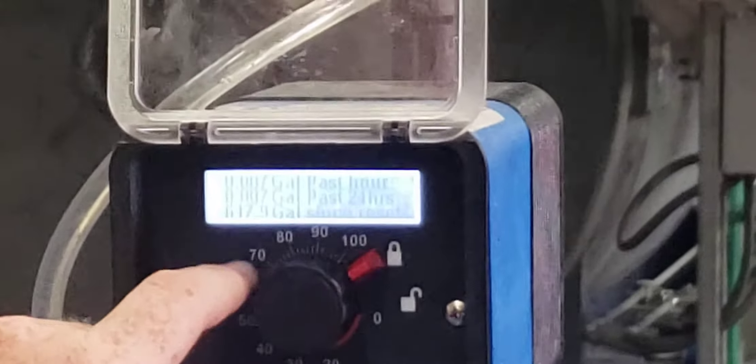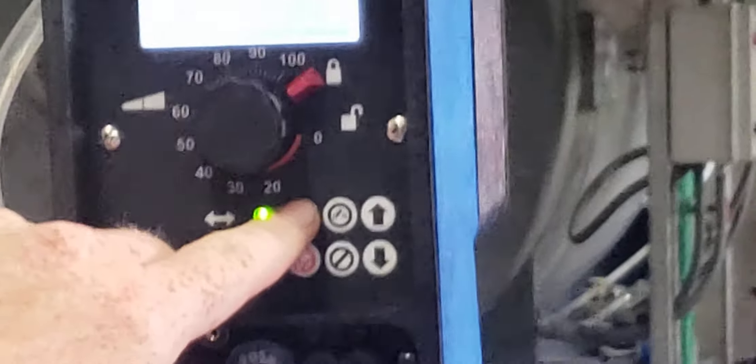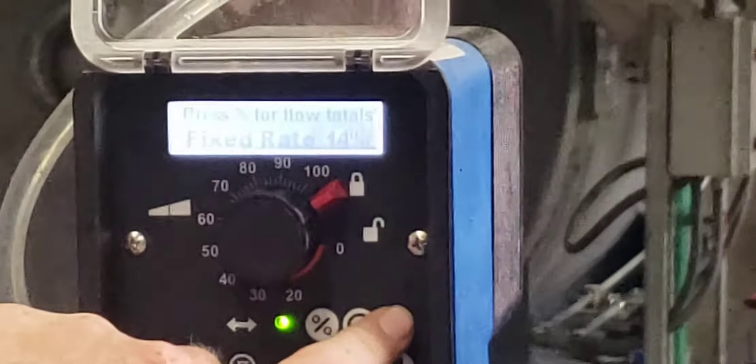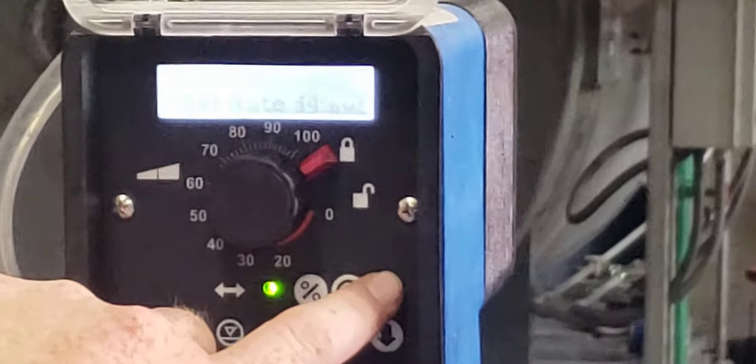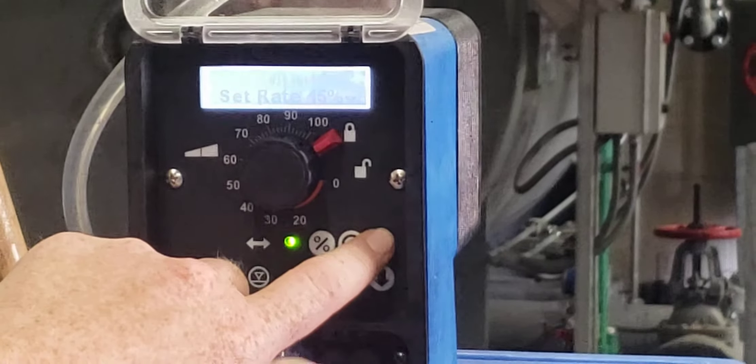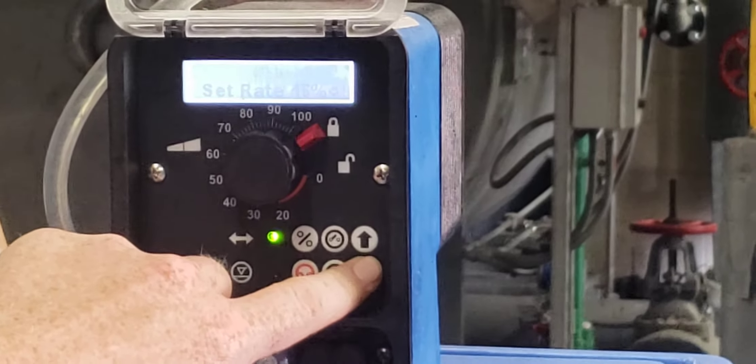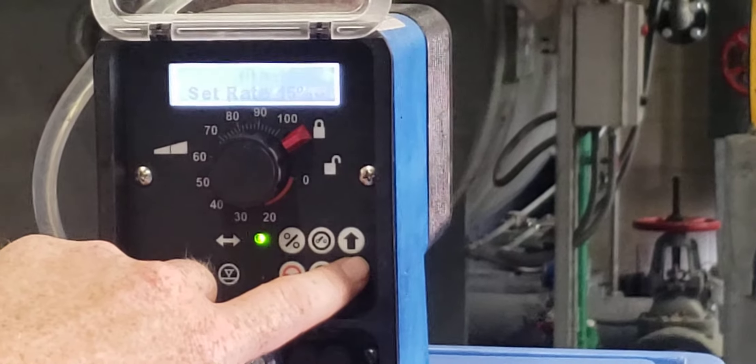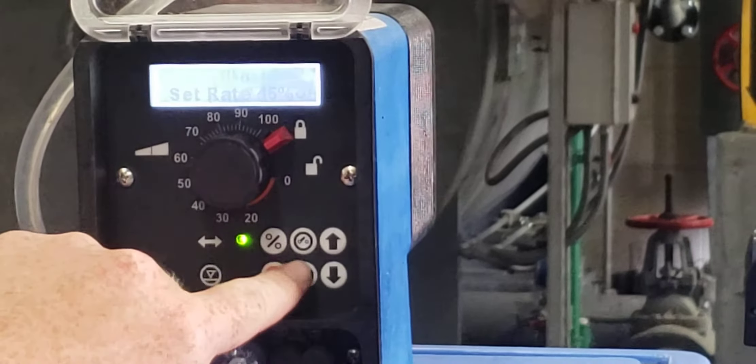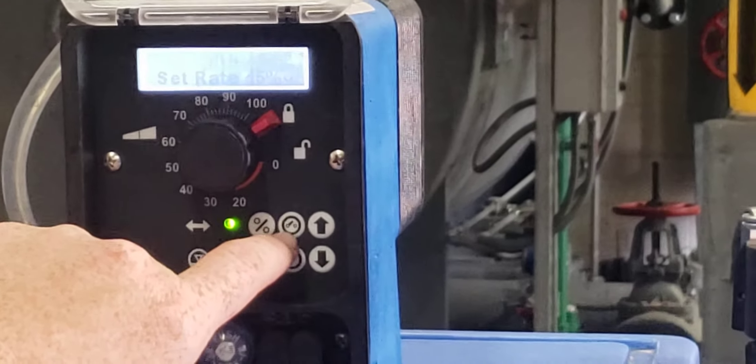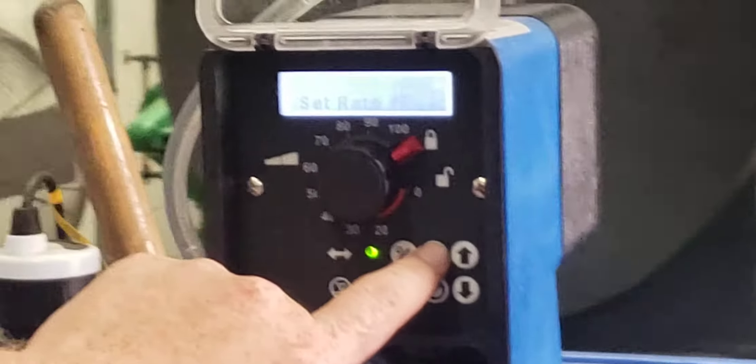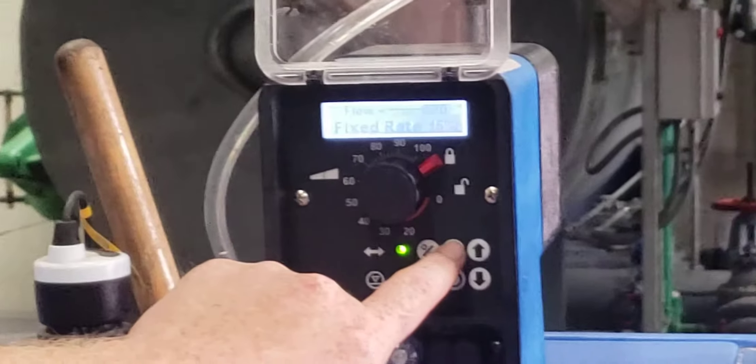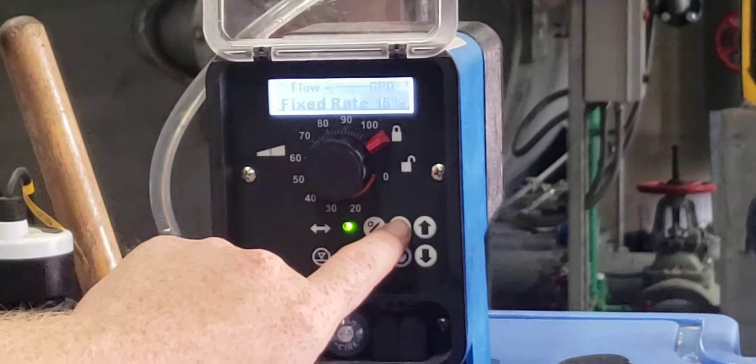This also tells you the history. If you hold down the percent button and arrow up, the pump's going to stop running. At this point you can click to the exact speed that you want to set it. Then you're going to click what looks like a thermometer with a water drop coming out of it, and that puts it back into the mode and back into operation.